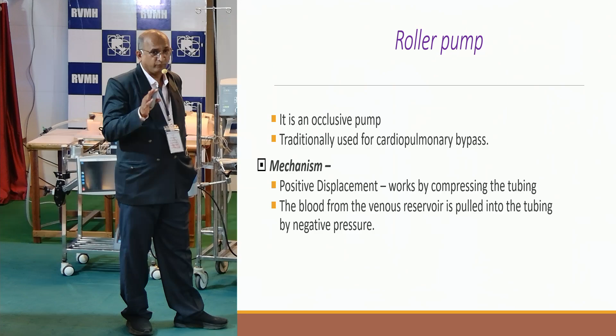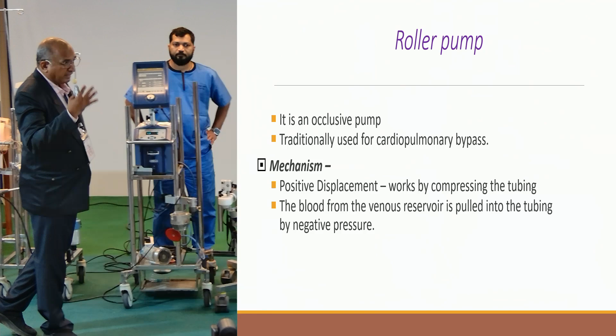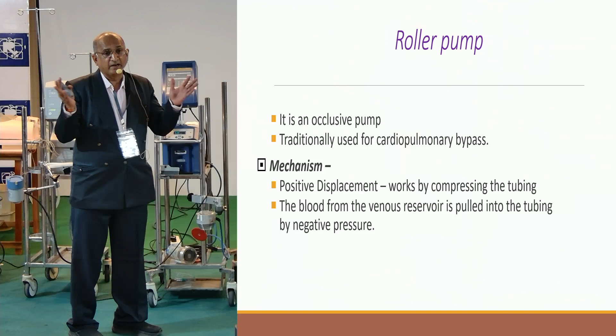So it will squeeze the tube and make the blood move forward. Okay. The problem with this pump is it is not based on your preload and afterload. So it is independent of preload and afterload. Okay. So when patient is hypovolemic, your pump moves, it will suck the intima and that will create a problem. If your return line gets kinked or blocked, it will keep on moving the same speed and it will create lot of positive pressure and your tube get ruptured. Okay. So these are the disadvantage of a roller pump.